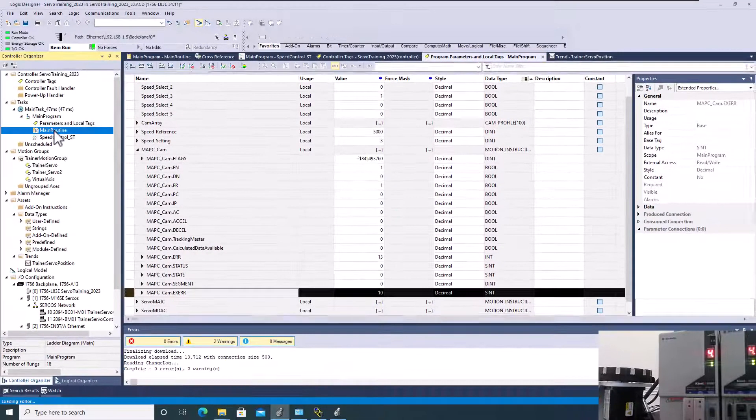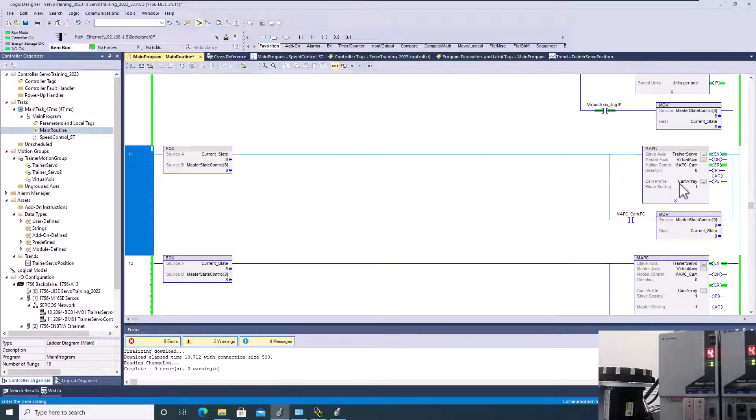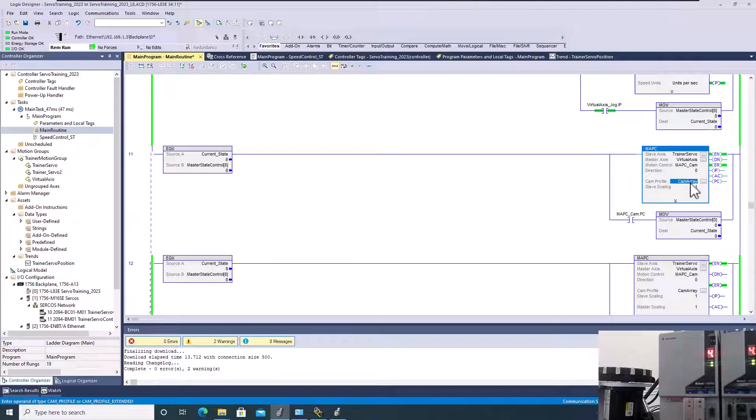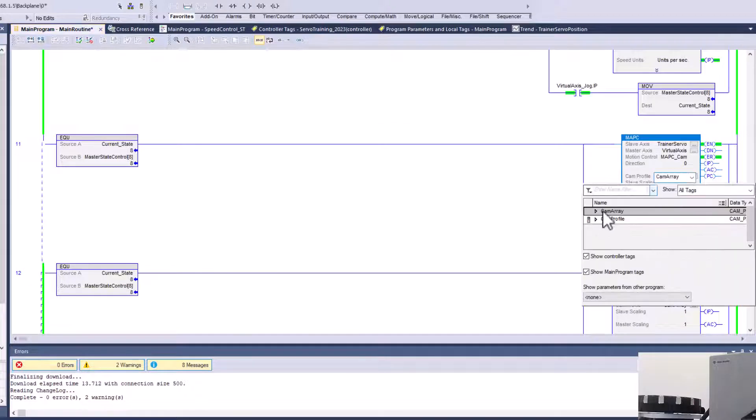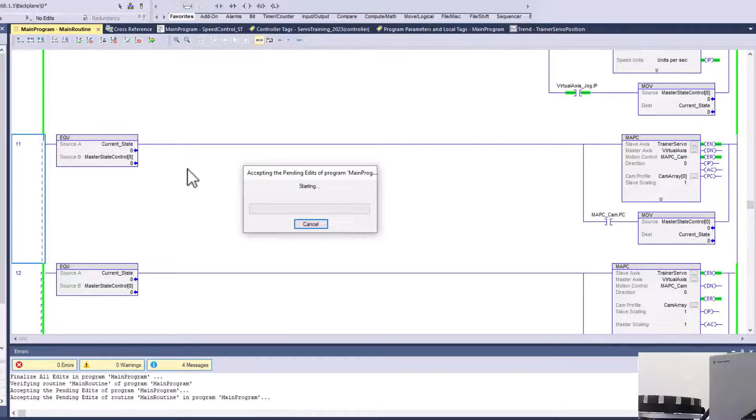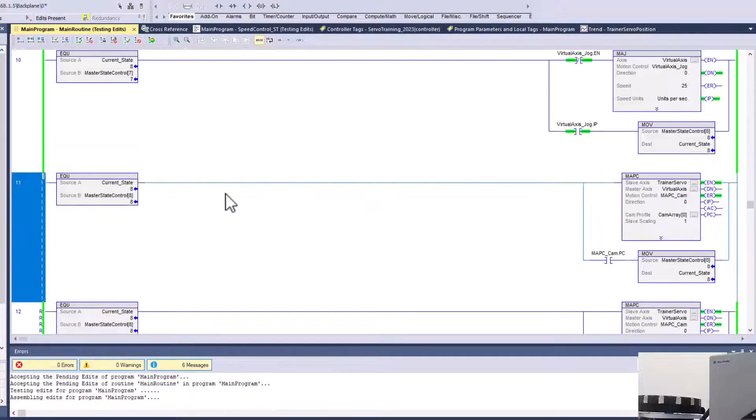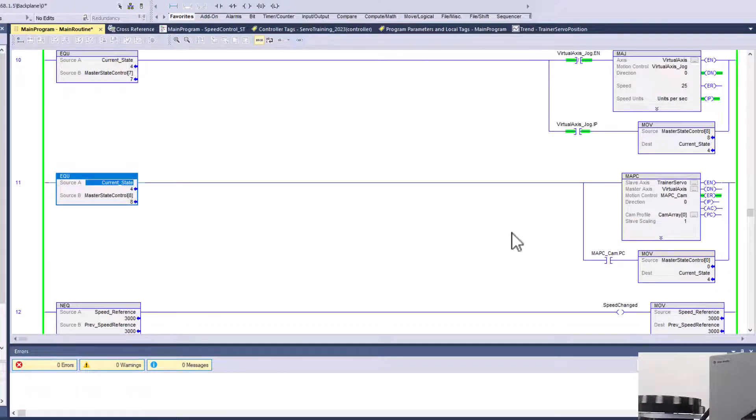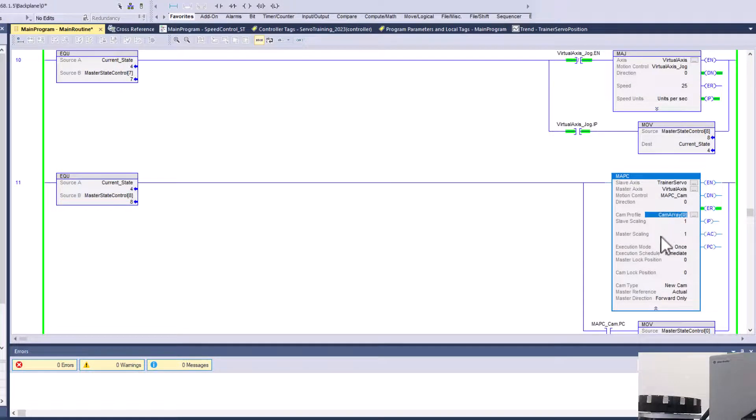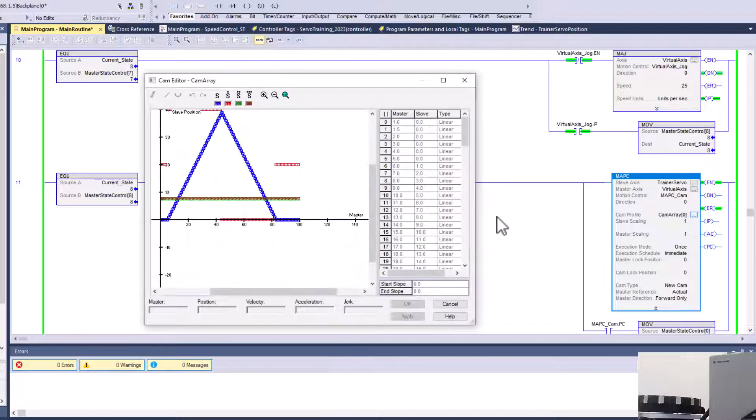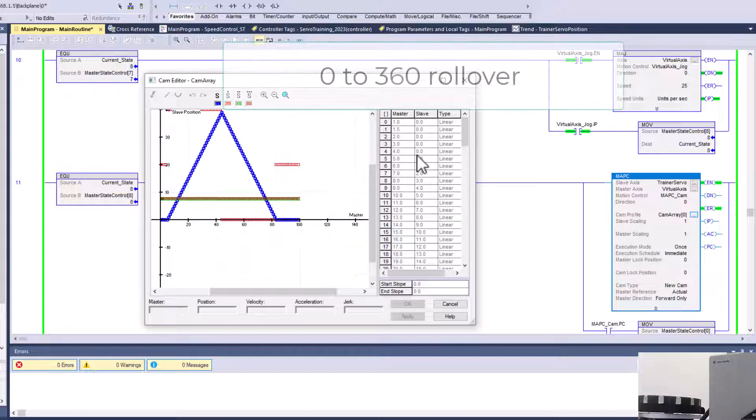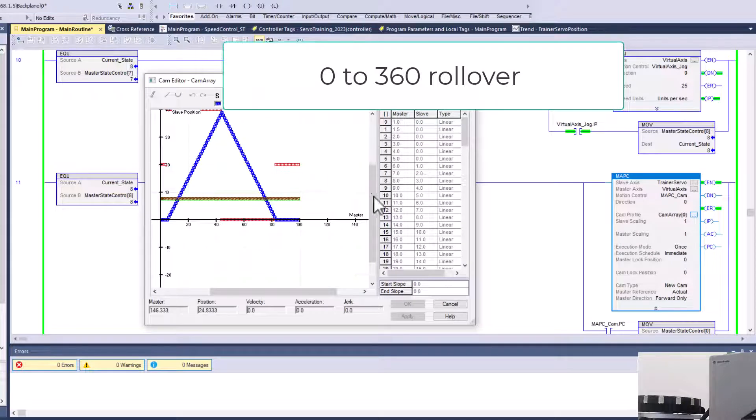So what are we going to do? We're going to come back in this. For one, we can easily come in here and change where this cam starts. So if we come over here, we can change where the cam starts. That's no problem whatsoever. So we're going to come over here and then we're going to reset our actual system. So let's actually go and put that back at four so that it goes to four. Now notice what we're trying to do here is first fix one problem that we can online, without having to go all back offline and download. So we will go to this. So now it's going to come to eight. It still has the same problem.